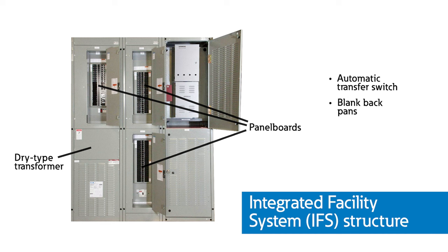Last but not least, an integrated facility system switchboard structure includes panel boards, dry type transformers, transfer switches, and blank backpans for field mounting other equipment. The IFS is helpful to integrate other equipment into a switchboard. In most installations, switchboards are mounted close to the wall and are front accessible only. If required, the switchboard can be constructed to allow both front and rear access.